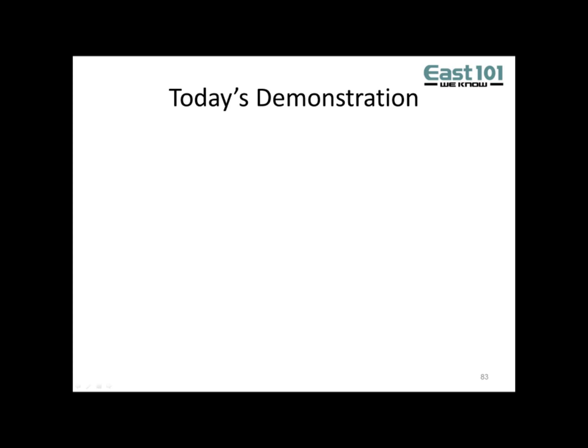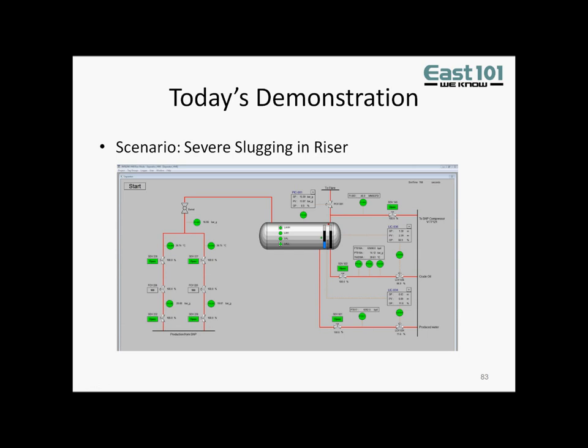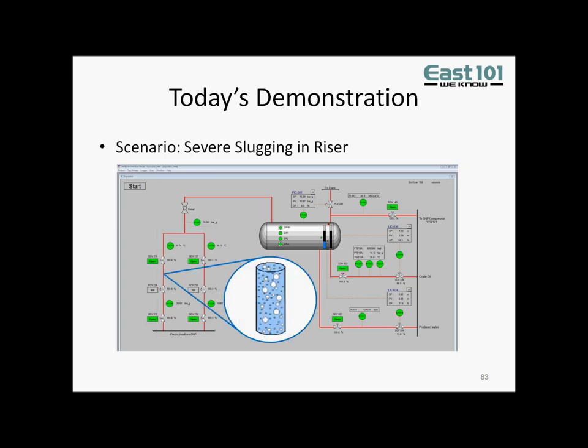Before we begin the actual demonstration, here is some background information on the case. The scenario being presented is one of severe slugging in the riser, which is shown in the black rectangle. The facility is an FPSO producing during early field life, which requires gas lift to operate. As long as there is gas lift, production is generally steady. If there is a sudden loss of gas lift, severe slugging is expected. This is characterized by large oil slugs, followed by surges of high pressure gas entering the inlet separator.